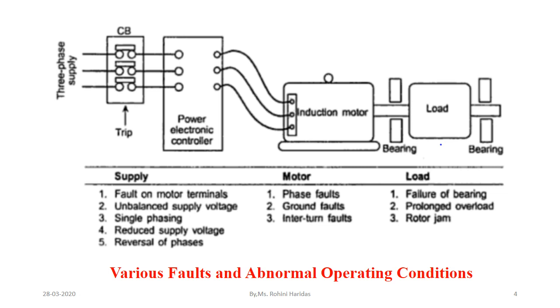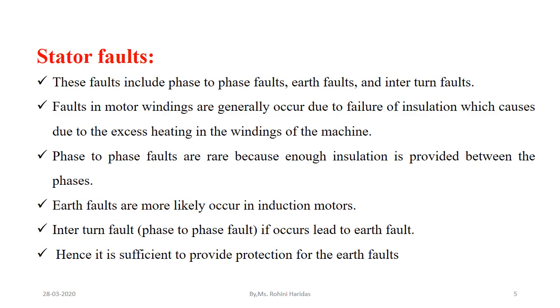On the supply side, faults include: faults on motor terminals, unbalanced supply voltage, single phasing, reduced supply voltage, and reversal of phases. In the motor itself, faults can be phase faults, ground faults, and interturn faults. On the load side, there may be failure of bearings, prolonged overload, and rotor jam. Faults in the motor winding generally occur due to failure of insulation caused by excess heating in the winding.